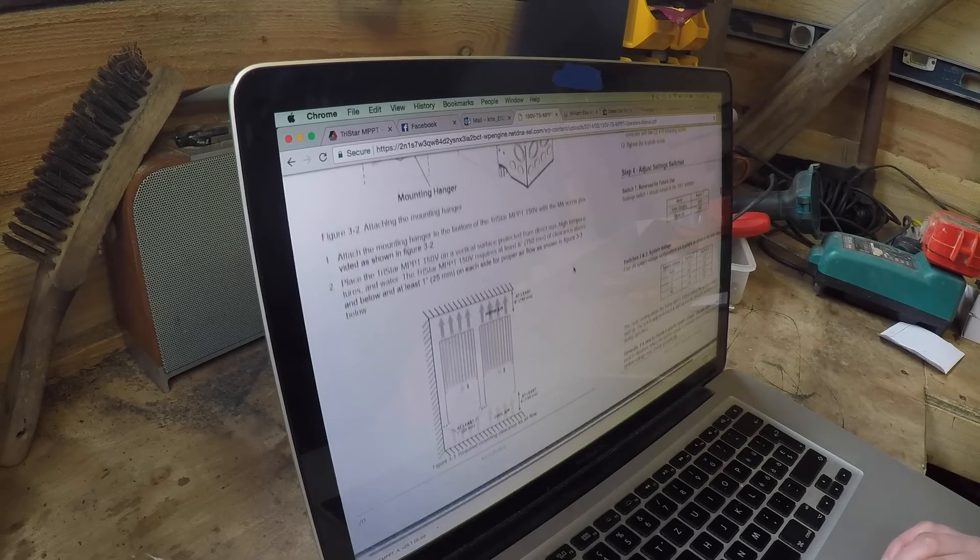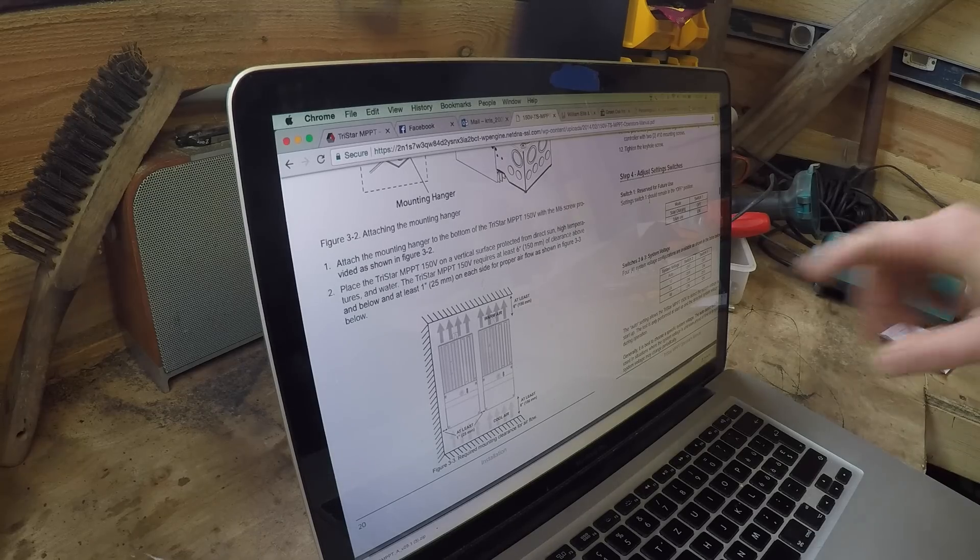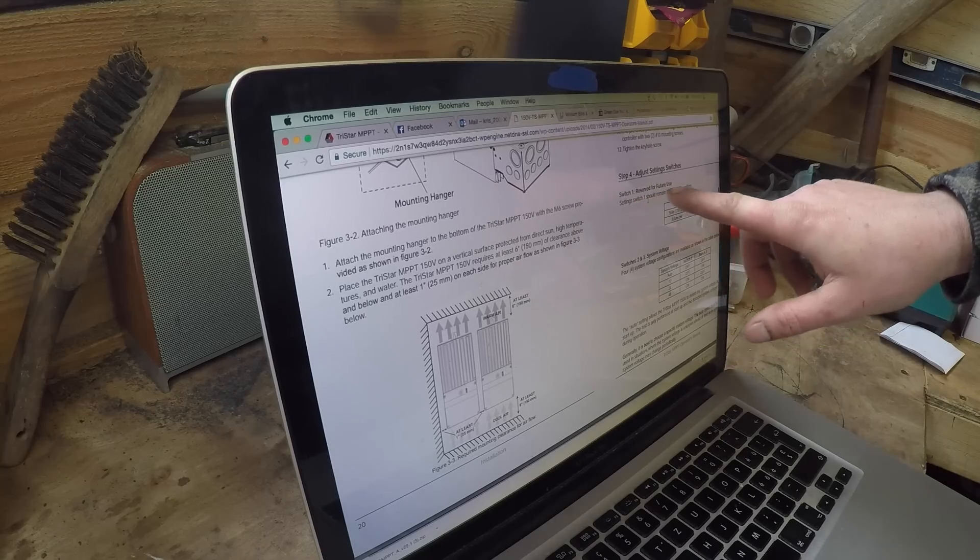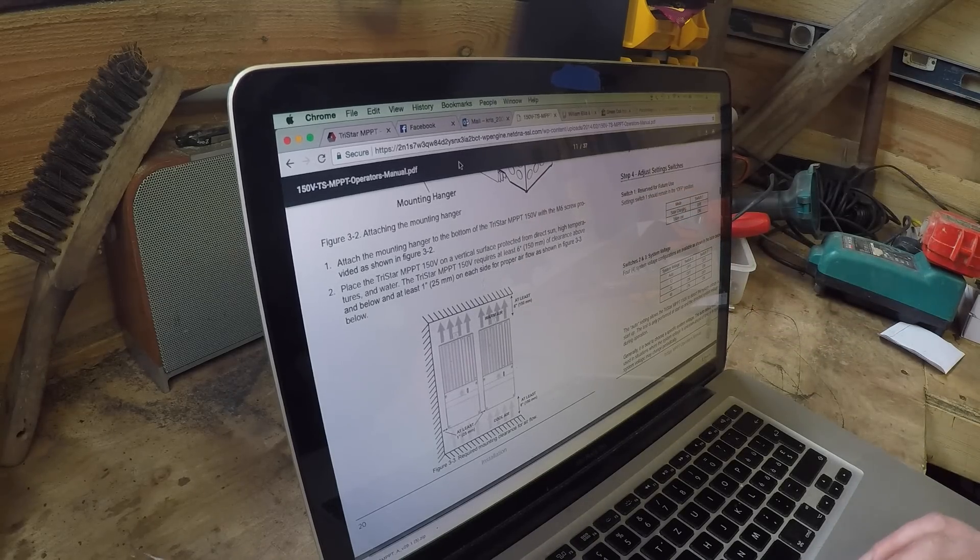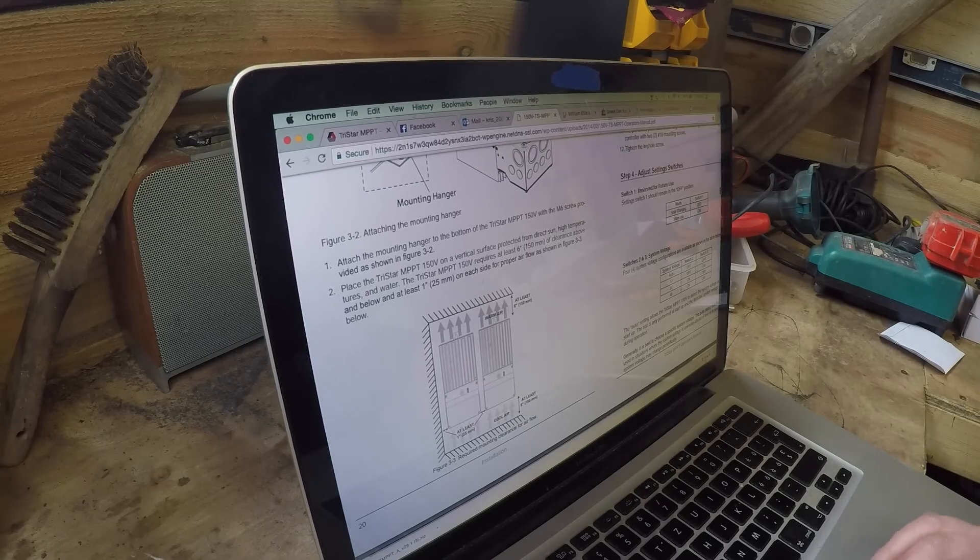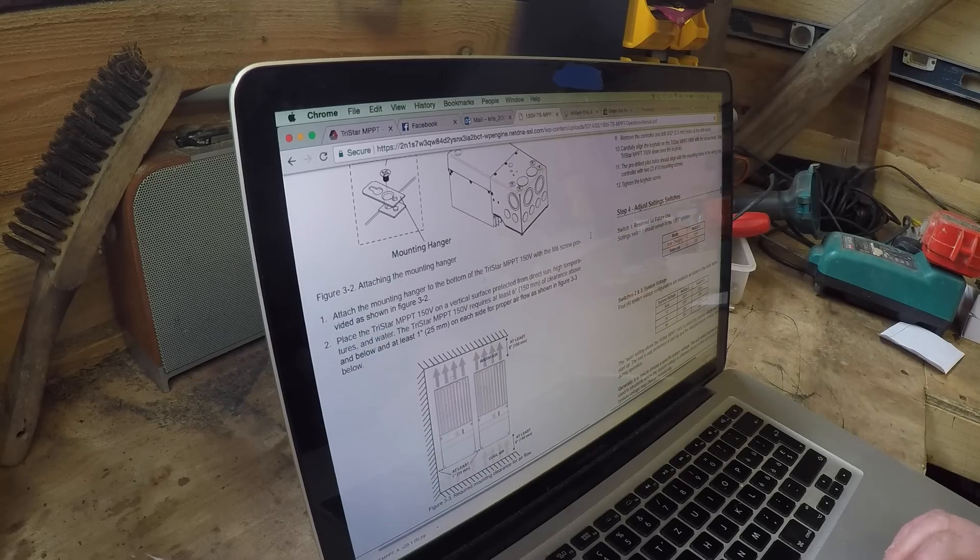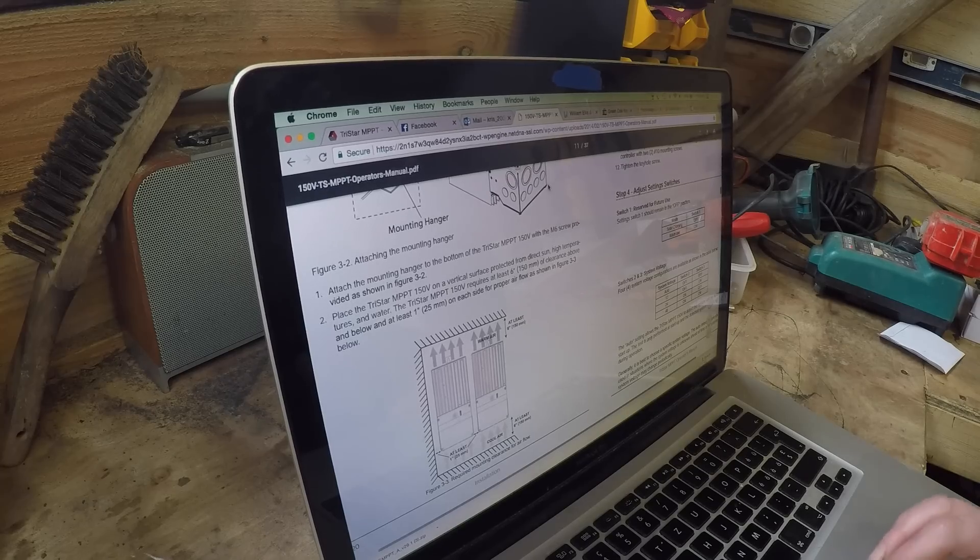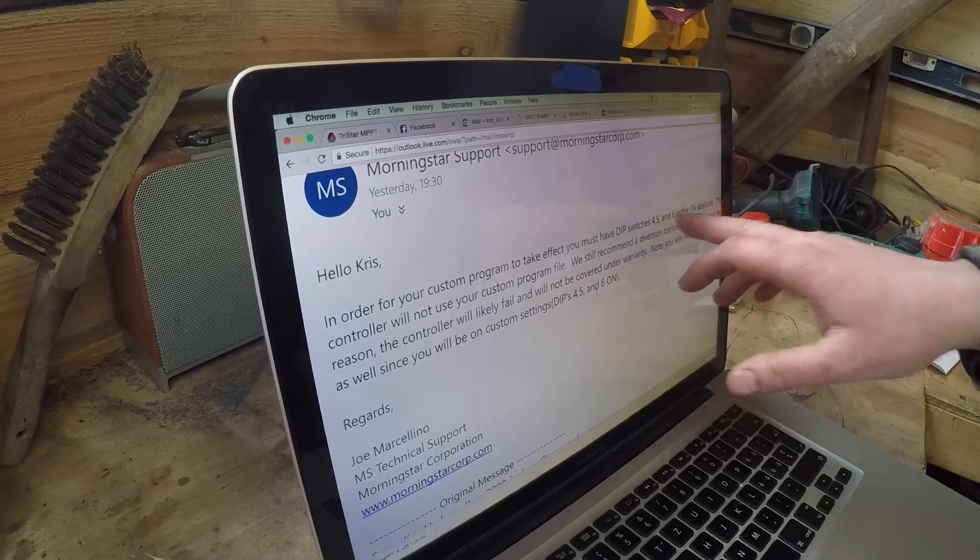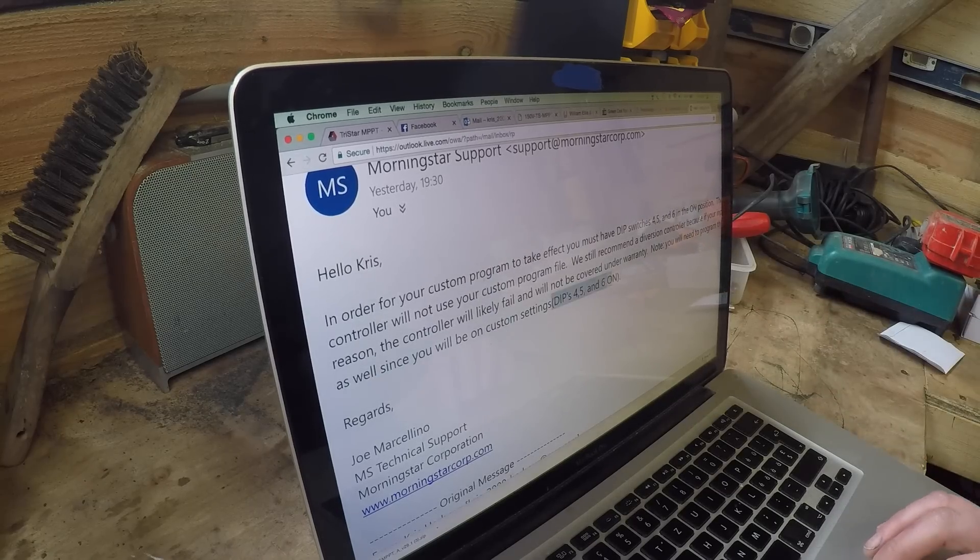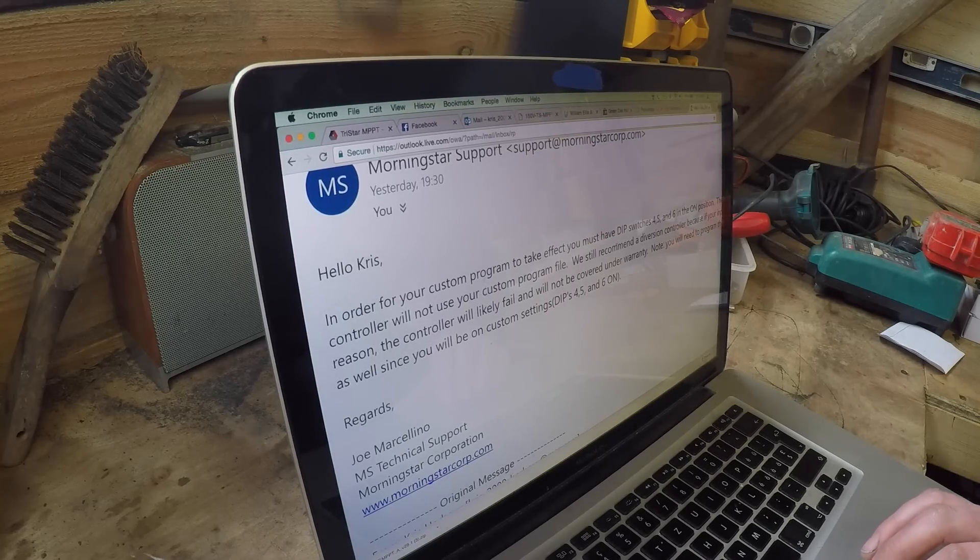If we look at what it says about adjusting setting switches, when you get the controller it says switch one reserve for future use, setting switch one should remain in the off position. That's why it was in the off position. But yet the other documentation about wind mode says it needs to be in the on position. So it's very confusing, the information is contradictory. The information I got from the support team was just talking about four, five and six which I haven't even changed because it's now working when I just put the first dip switch to the on position.